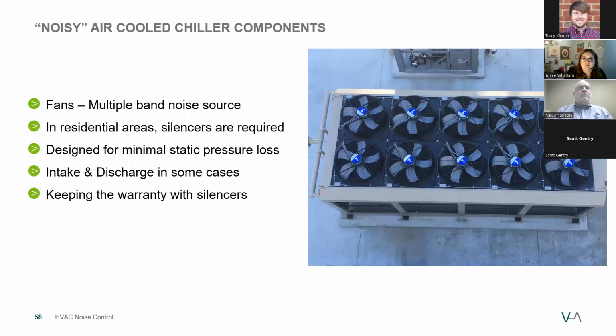So next are the fans, producing the most noise in an air-cooled chiller. You would need to consider that the cooling fans can produce multiple broadband noise. When units are near residential areas, silencers are usually required based on the proximity of people and the lack of space. The circular and rectangular silencers are custom designed for minimal static pressure loss, and they can also be found on the intake and discharge at the same time in some cases. And finally, it's absolutely possible to keep the unit's warranty intact when adding silencers to an air-cooled chiller.